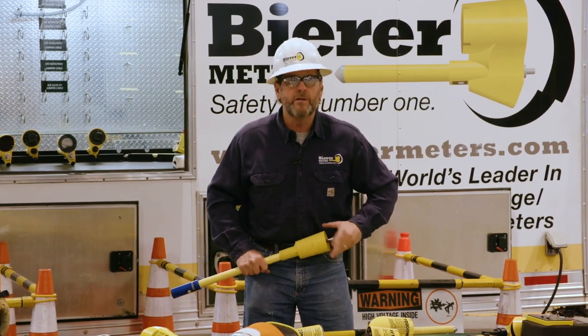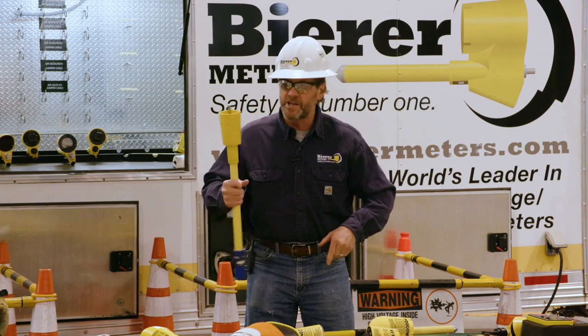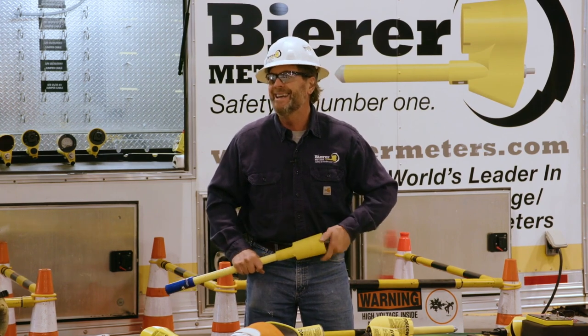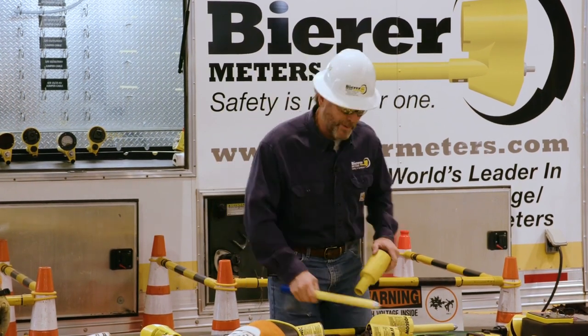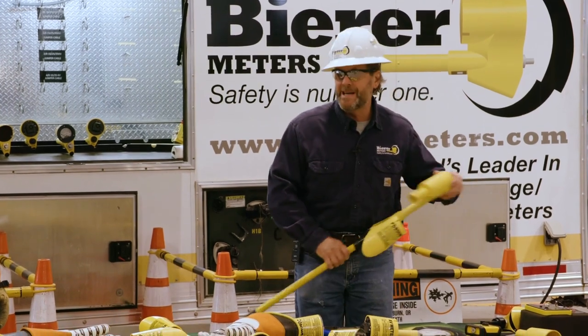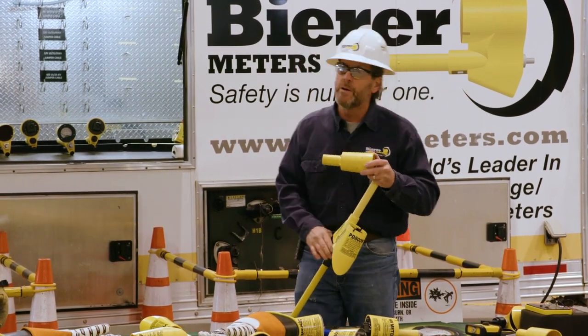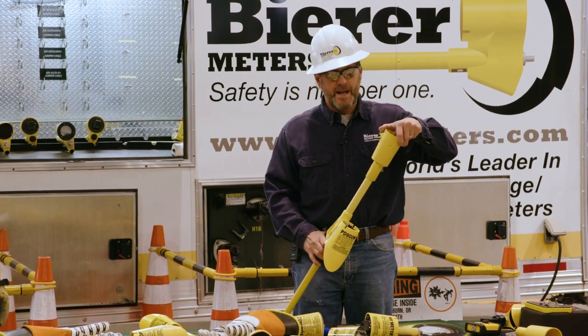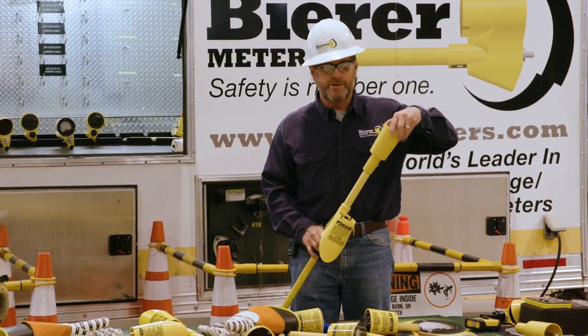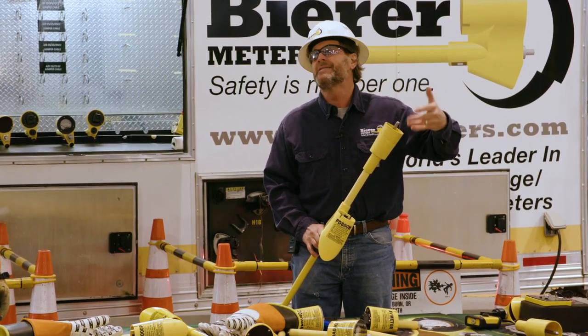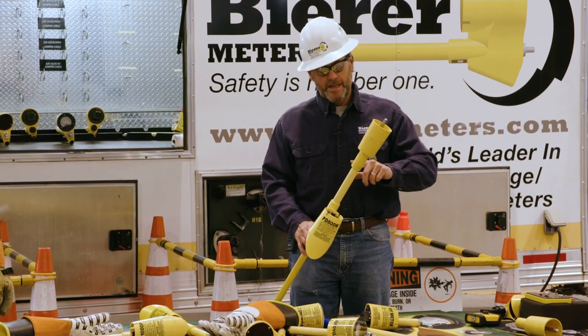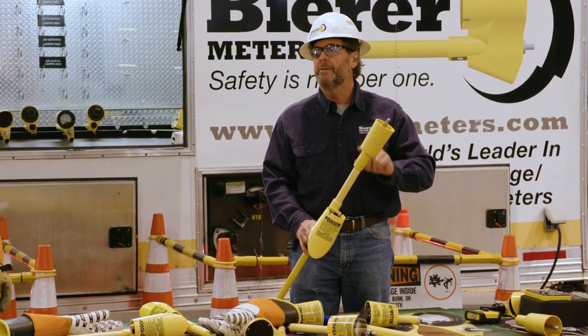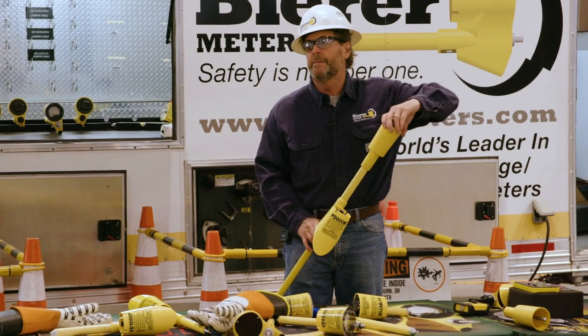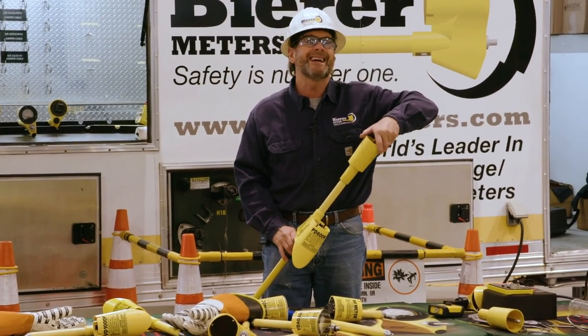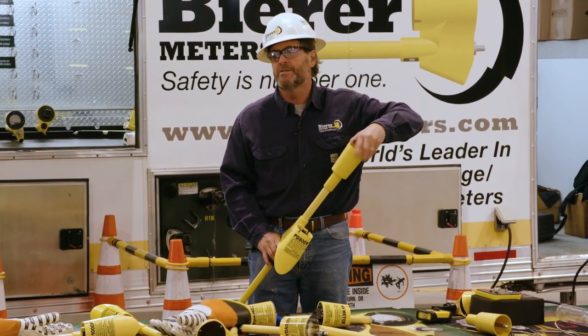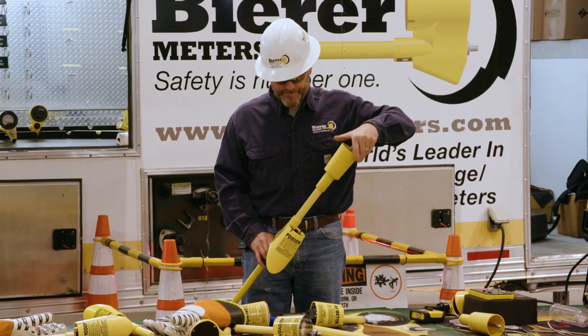So Robbie's going to use the bushing adapter on the end of the cone tip, which is improper when you're going to capacitive test points or secondary voltages, because it's not a feed-through or a hot bushing. It's improper, but it's still safe because it reminds you of that line limit, and we're keeping our distance from passing the line limit. Plus, we're saving a couple of seconds here by just using one accessory, okay?